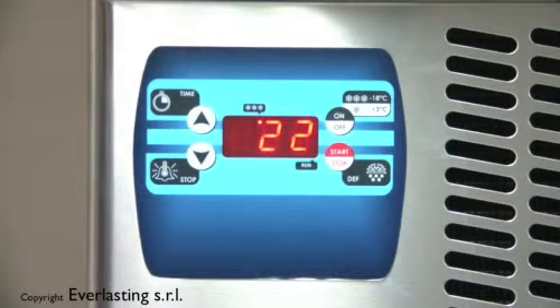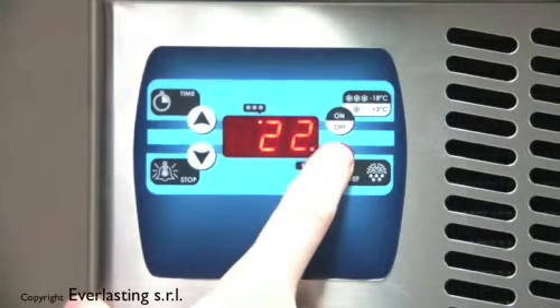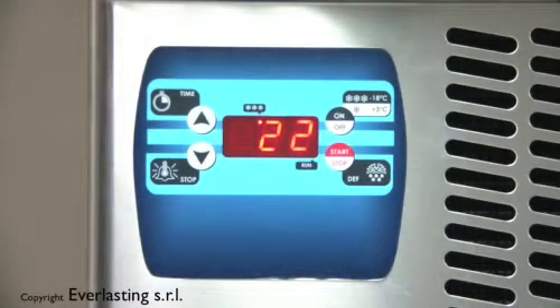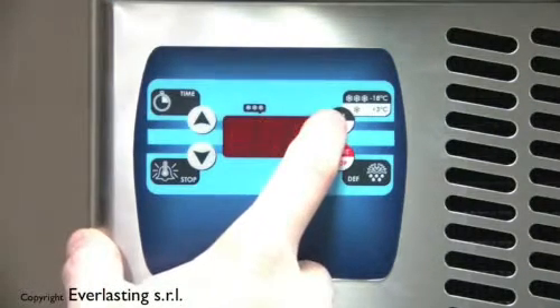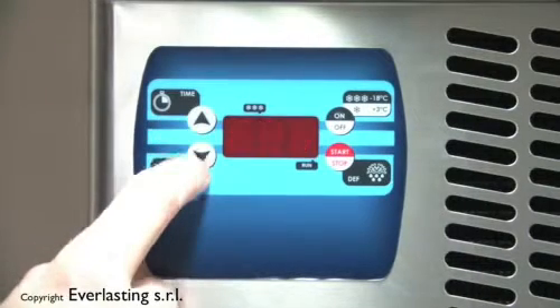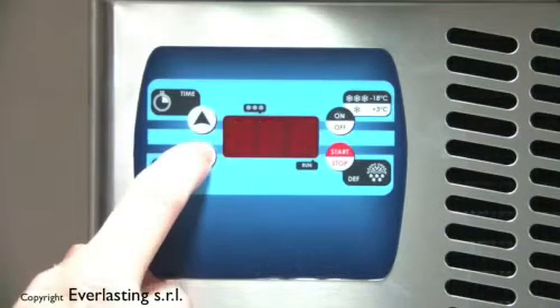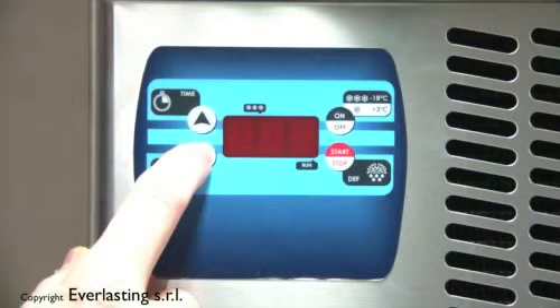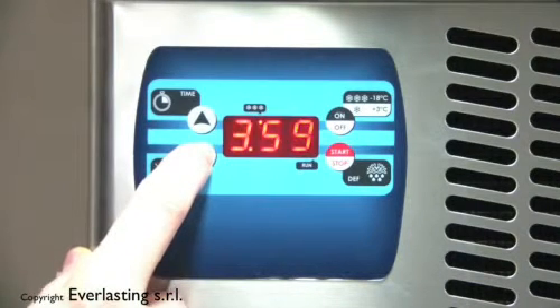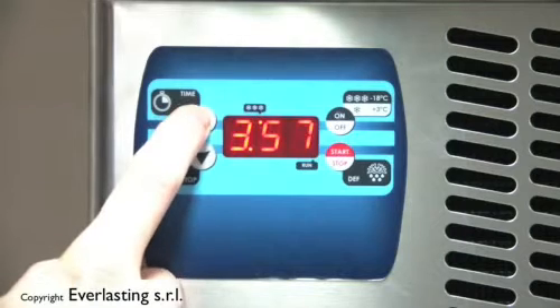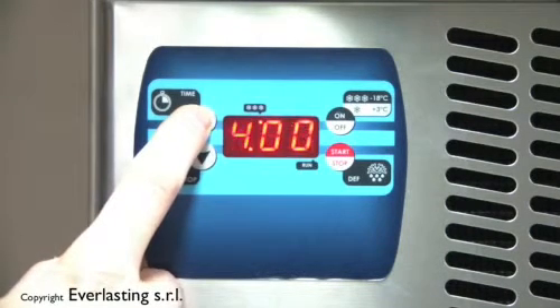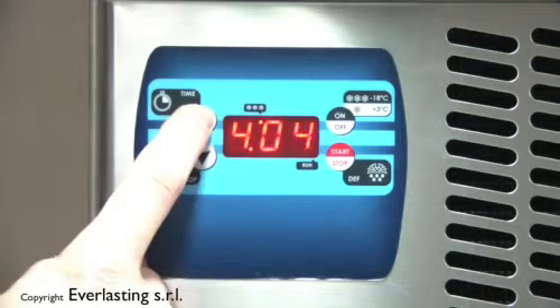How to select a timed cycle, without the use of the core probe. The same cycles can be selected in time mode, without the use of the probe. In the versions without the core probe, cycles are set by default. Select a negative cycle of blast chilling. Pressing the on-off key, then the up arrow time key, the operation is automatically set to a default duration of 4 hours. If a shorter time is necessary, change it directly with the cursor. In this case the machine is set for a 3 hour cycle.